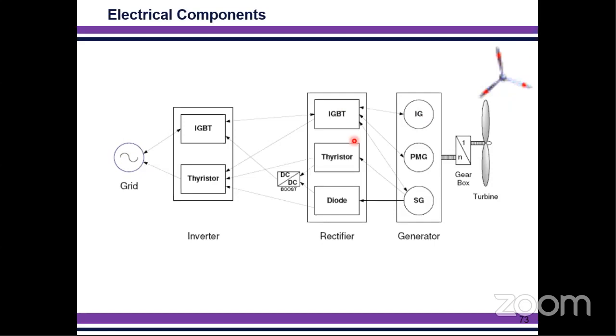So I have given the arrow. In the arrow you can easily understand which converters are suitable for which generator type. Only specific converters are suitable for specific generators, so that's one important thing. Especially the induction generator requires reactive power support, or you can say excitation. Whereas for the synchronous generator and the permanent magnet, it is not of much importance, so you can go without excitation. That's the advantage of going with the permanent magnet as well as the synchronous generator.